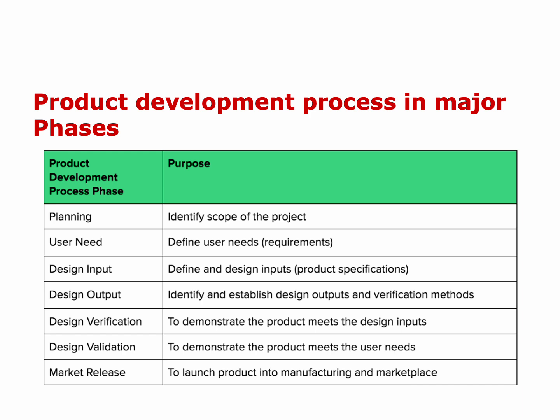Then for each and every functionality of the device, we are going to write down a statement to say, okay, test this function in the device. If function A is working, in the column in front of that functionality, we're going to check, yes, this is done, validated. So we will continue to go over each and every functionality of a device, and we are going to write in front of that functionality that, yes, after testing, the device is working. This is how we do the validation, and we are going to document that.